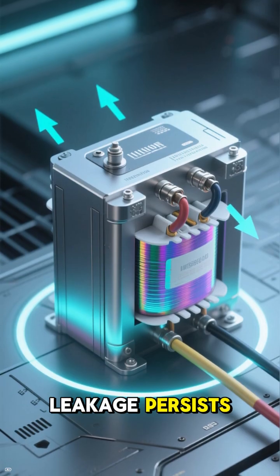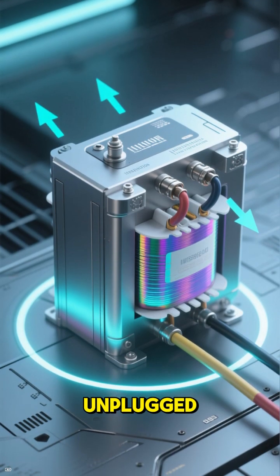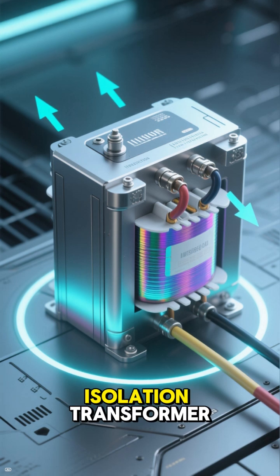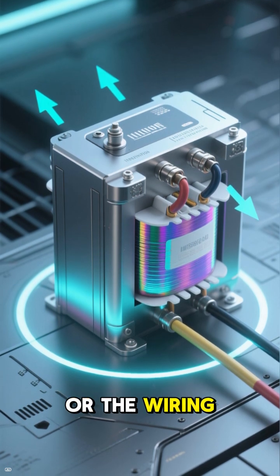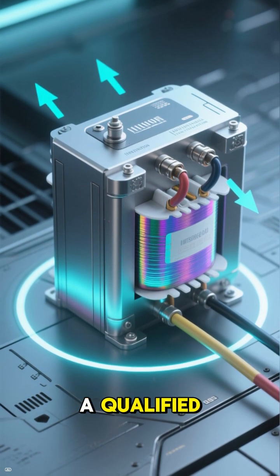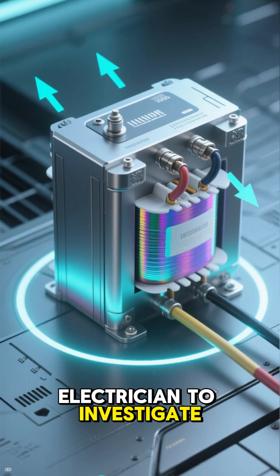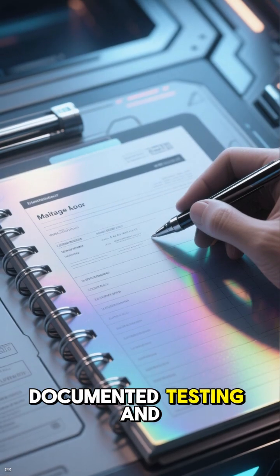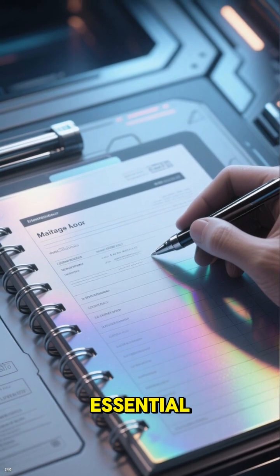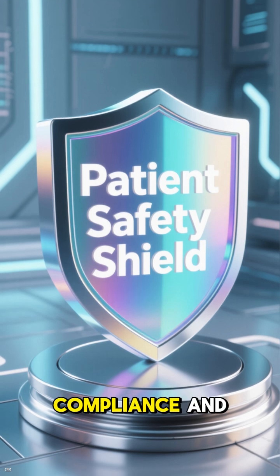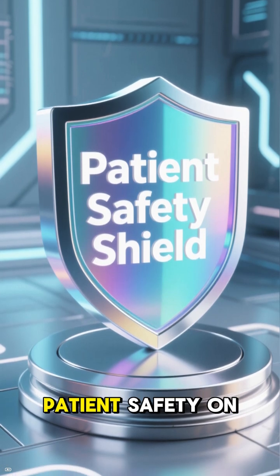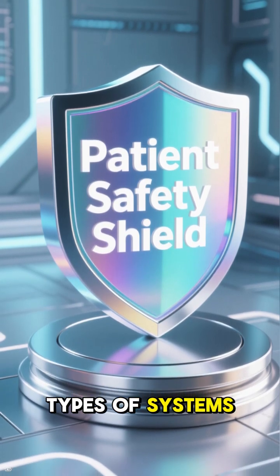If the high leakage persists, even with all equipment unplugged, the issue might be with the isolation transformer or the wiring itself, which would require a qualified electrician to investigate. Regular documented testing and diligent maintenance are absolutely essential. It's the only way to ensure compliance and, more importantly, patient safety on these types of systems.